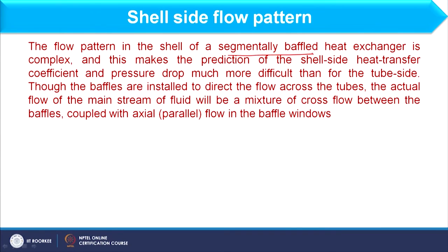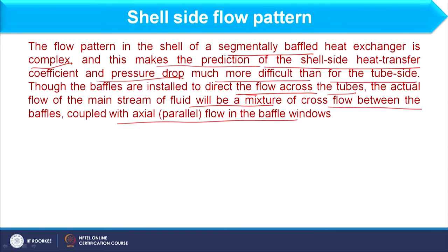Now, let us see how to estimate the shell side heat transfer coefficient. Before going into detail of that, we will see what the shell side flow pattern should be. The flow pattern in the shell side of a segmentally baffled heat exchanger is complex, and this makes the prediction of shell side heat transfer coefficient and pressure drop much more difficult than that for the tube side. Though the baffles are installed to direct the flow across the tube, the actual flow of the main stream of the fluid will be a mixture of cross flow between baffles coupled with axial flow in the baffle window.